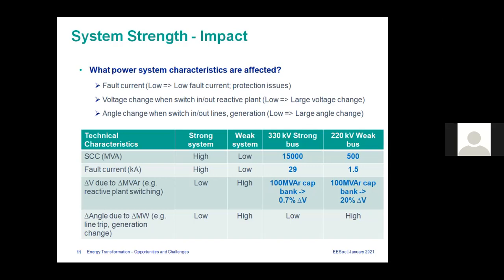So that's another issue. The lower the system strength or fault level, the higher the voltage change can be. And it's the same with voltage angle change. If there is a generation tripping or line outage, at low system strength locations you see a larger voltage angle change compared to a high system strength location. When there is a large angle change, the voltage angle can move towards the unstable region easily. So this can be a problem in low system strength locations compared to high system strength locations.